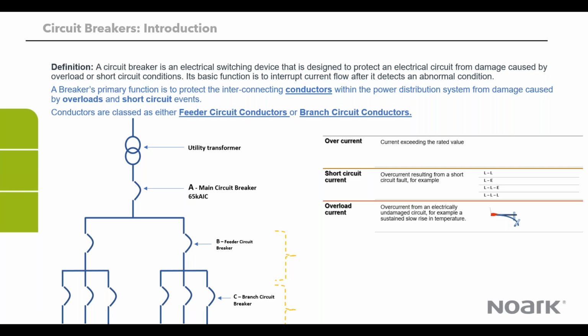From the definition of a circuit breaker, you find that a circuit breaker should also be able to work under normal conditions. We've talked about an abnormal condition. Basically, a circuit breaker should be able to carry current, it should be able to maintain current, and then it should finally be able to interrupt current, under normal and also abnormal conditions. And primarily a circuit breaker is meant to protect the interconnecting conductors in a power system. We have two types of conductors: the feeder circuit conductor and also the branch circuit conductor.